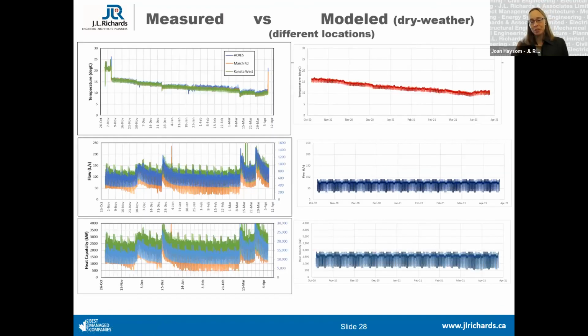So here's a comparison between where we went ahead with modeled data versus measured data. You're familiar with the left-hand side already. The right-hand side is one of these, but we synthesized it to avoid the wet conditions, so we called it a synthetic temperature profile. One point I didn't mention is you can see the seasonal drop in wastewater temperature across the winter. Interestingly, when your peak heating season is January, February, that's not your lowest point. Your lowest point in wastewater temperature is down in spring, March, April, in the shoulder season. The flow model we received is a single daily 24-hour profile that we repeated.